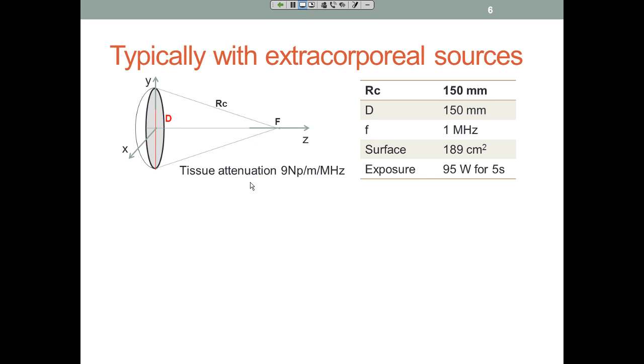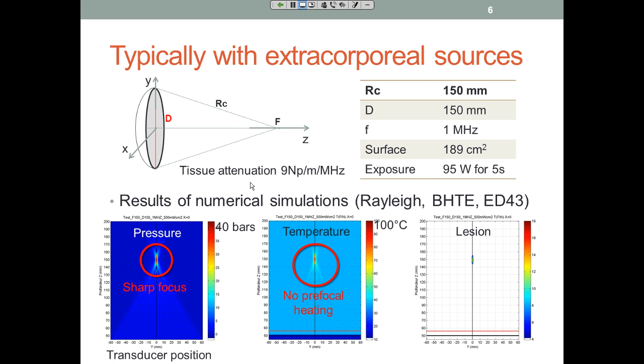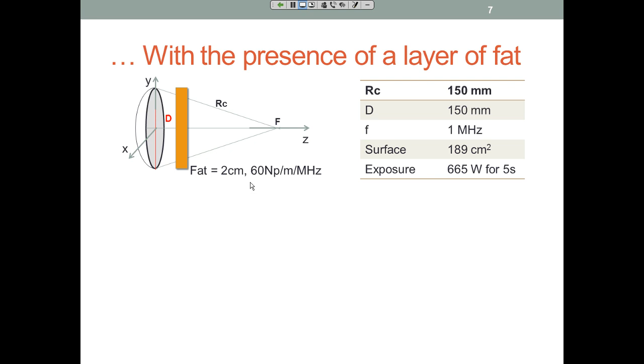So if you want to reach a temperature of 100 degrees at the focus with this transducer, you must use around 100 watts for 5 seconds. So you have a sharp focus, no prefocal heating. If you place a layer of fat between the focus and the transducer, you see this fat layer is very attenuating.